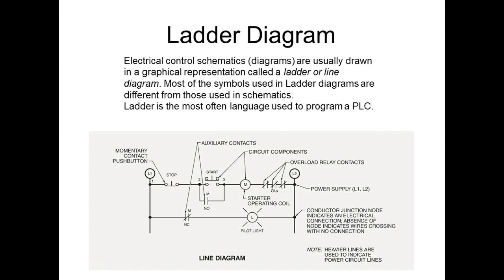So what I would have to do is fuse it to let the motor start. Well, the problem is if the motor stalls, it's going to pull the same current. So if the motor doesn't start, or if it stalls, it would sit there and just burn up, and the fuse would never blow, because it's rated to let the motor what? Start. So they had to come up with a method where we had some device that senses overcurrent over time. So we could draw current, we could let it start, but if it tried to pull that 30 amps for 10 seconds, it would kick out the circuit. And this is what overloads do.